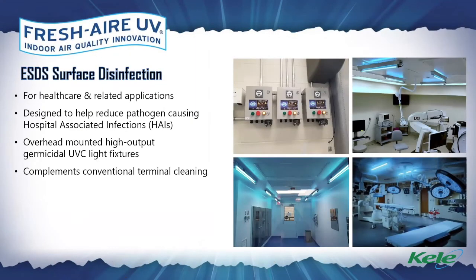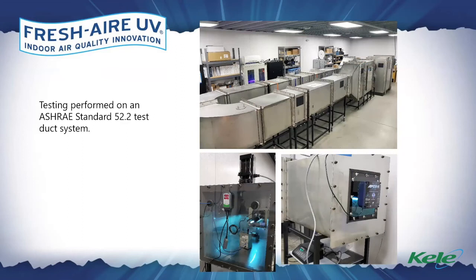The BTXL can also be used for ceiling and wall mount applications. And certainly in March and April of last year, we could not even keep these systems in stock. They were being used to complement terminal cleaning practices for high touch surfaces. I know they were using them for rooms where they would mount them on the ceiling and the wall, and they would put all the N95s on a coat rack, and they would wheel it in and then spend a few minutes irradiating the PPE. They were using these in all kinds of innovative means. But all this to say is that the BTXL can be used also for these innovative room type applications for unoccupied spaces.